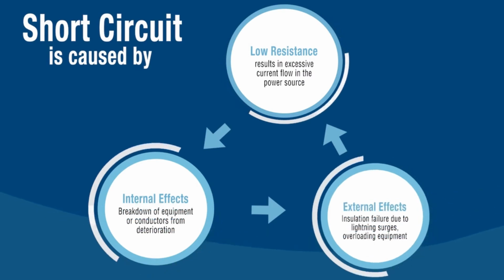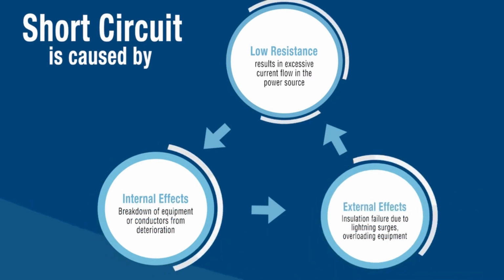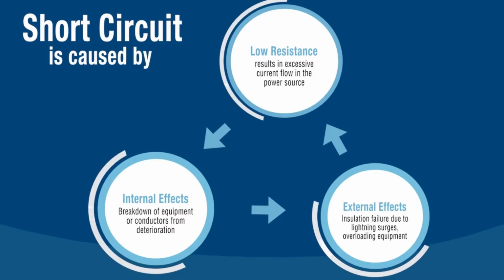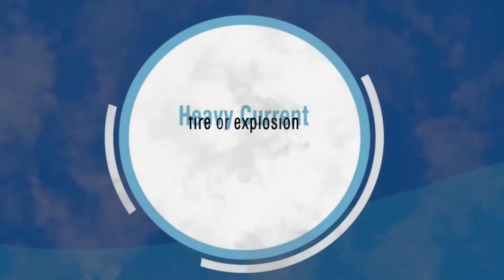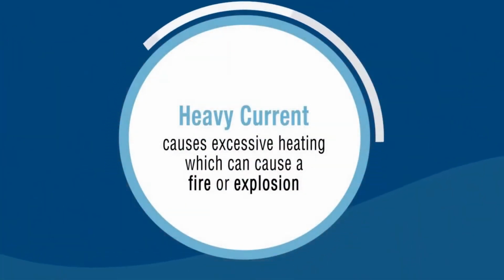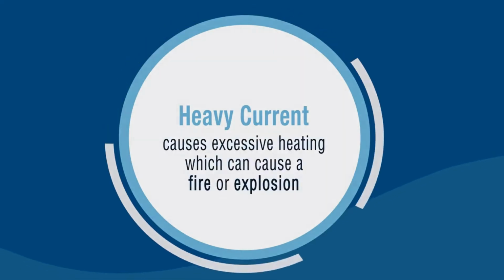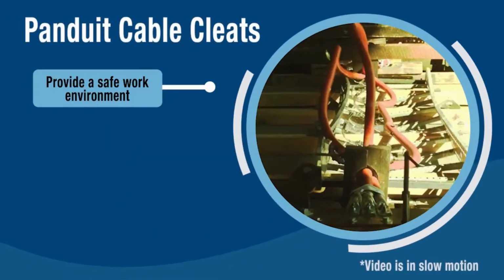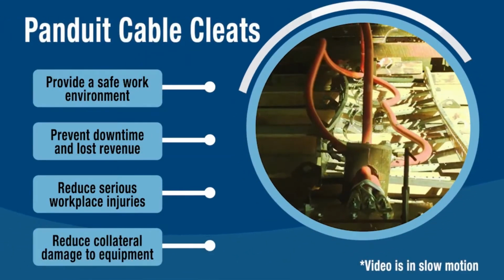When a short circuit occurs, current in the system increases to an abnormally high value, while the system voltage decreases to a low value. The heavy current causes excessive heating, which can cause a fire or explosion in just a split second. A short circuit is powerful enough to cause cable and equipment damage.